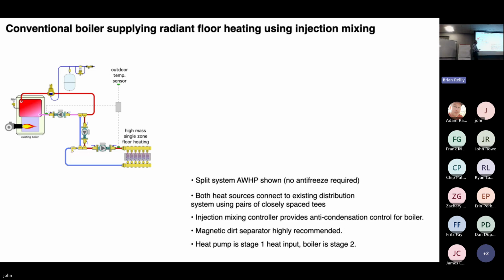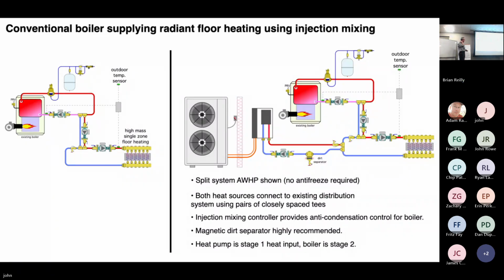This is a way to do low temperature floor heating with a conventional boiler without requiring a mixing valve, like a 3-way or a 4-way mixing valve. We've designed many systems around this. So let's say you run into this in the field and you want to add the heat pump to it. Start over on the right side. I've left this whole thing intact. Haven't started to cut pipes here, but right here, I've put in a pair of closely spaced T's.